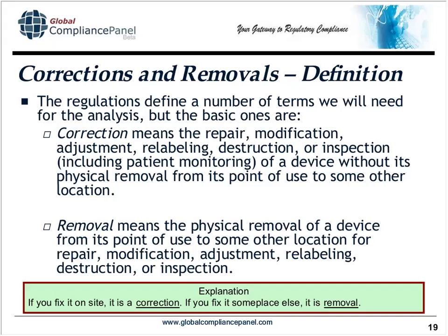Here are the key definitions. A correction means a repair, modification, adjustment, relabeling, destruction, or inspection of a device without its physical removal from the point of use. A removal means performing those same activities but taking the device away from where it's being used. FDA wants to know which ones you're doing, and you might be doing both. For example, if a hospital is close to your factory you might send someone out to do a correction on-site; if the hospital is remote or in another country and you want the device sent back, the same activity would be classified as a removal.